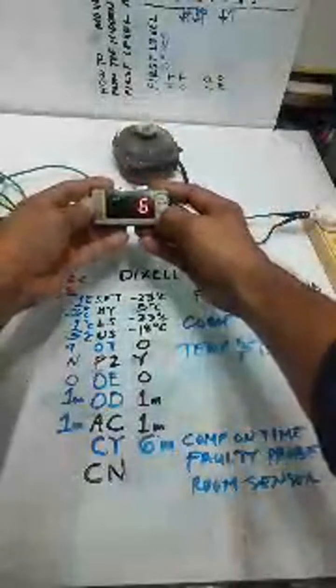Okay, take note guys, OD I set to 0 because I'm monitoring if that will activate by time right now, because last time I just put 1 minute here for our AC. Look what is going to happen if we set that to 0. Compressor is always off, so the CT parameter will not happen once you put that to 0.